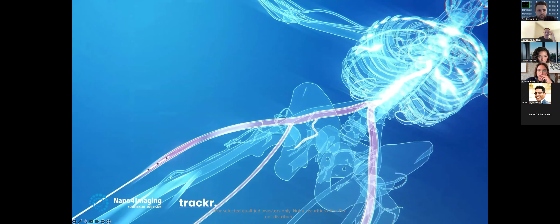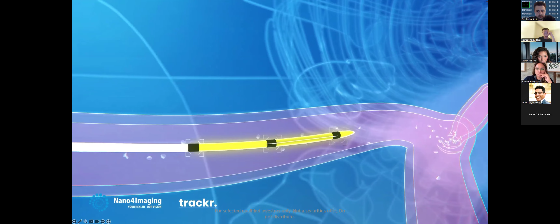In this case, a guide wire with 3 tip markers with a specific distance from each other is inserted via the femoral access and moved slowly upward towards the predefined stenotic area. Our software traces the number and distance of the markers. Just like a GPS system, it traces the position of the device through the tip. Even when the markers go out of the selected plane, the software will detect the 3 markers and show the position due to the 3-slice scanning.